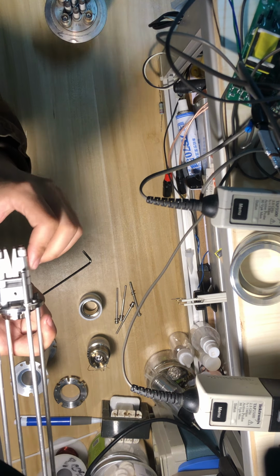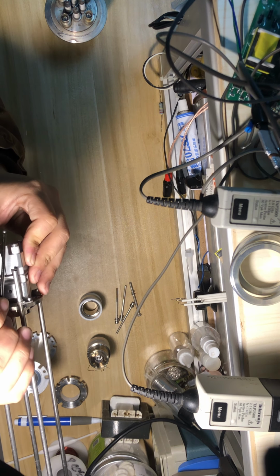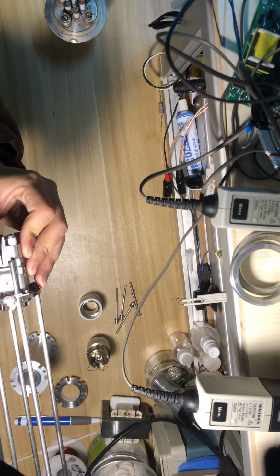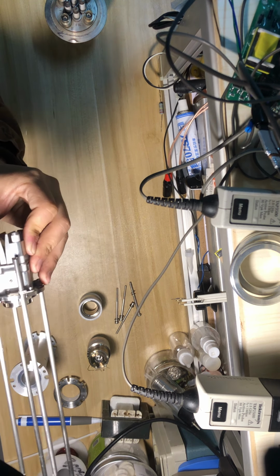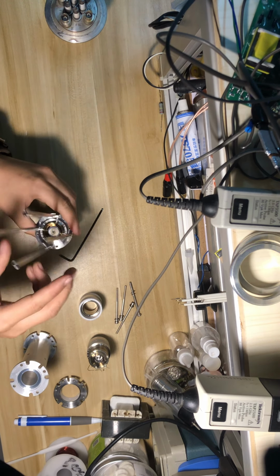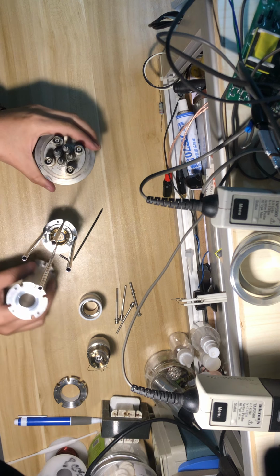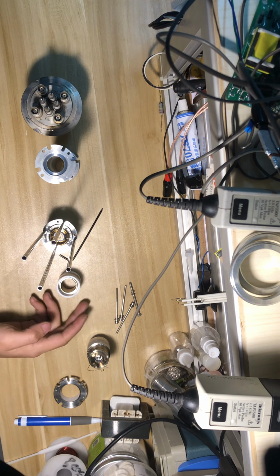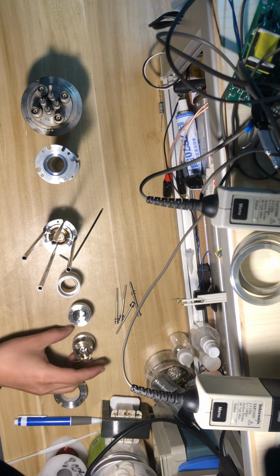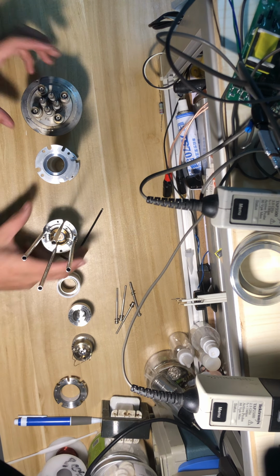The electron beam is actually negatively charged. So if this is positive, the electron beam will be deflected in this way. If this is positively charged, the electron beam will be deflected in this way. So in this way, we can create a scan pattern. Okay, so here is the whole assembly of the electron gun. You can see the focus, first anode, Wehnelt cap, and the filament.